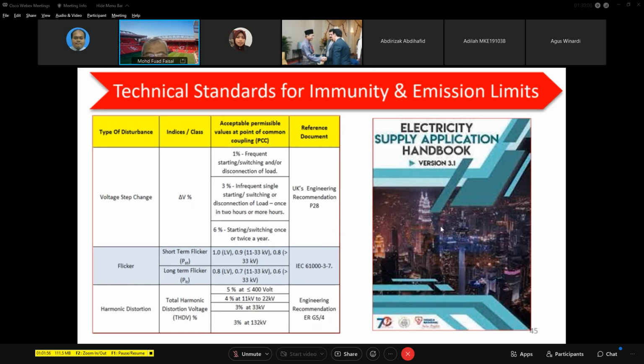Flicker has two items, short-term and long-term flicker, PST and PLT. The limits are shown here. Based on voltage, 1.0 is for LV, 0.9 is medium voltage, and 0.8 is above medium voltage. For long-term flicker, 0.8 for LV, 0.7, 0.6. These are very important to ensure the industry does not emit emissions that can affect other industries. That's the concern now. Some of these PQ disturbances are generated by another customer, so we don't want that to happen.